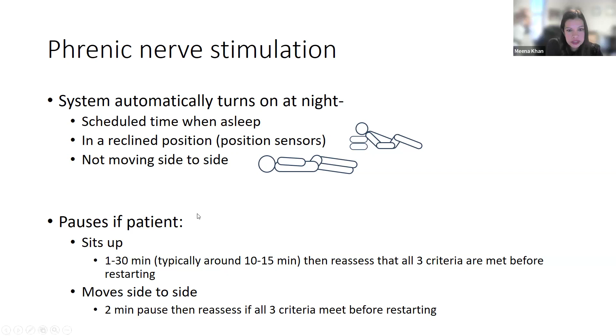So this is a schematic just to show how the therapy works. What is programmed into the therapy, and we'll go into more detail in the upcoming slides, is a target breath rate, which is usually the patient's wake breath rate minus 2. That's programmed into the device. And then there's a range of strength, which is measured in milliamps, that's programmed into the device. We'll talk about how you get to those numbers in the upcoming slides. But you program the target rate, and you program the milliamp range. Let's say 3.5 to 4.5. I'm just throwing that out there. So when the patient sleeps at night and it's time for therapy to turn on and it turns on, it will analyze the breathing. So here you see the Cheyne-Stokes, the central apneas, and therapy is off.